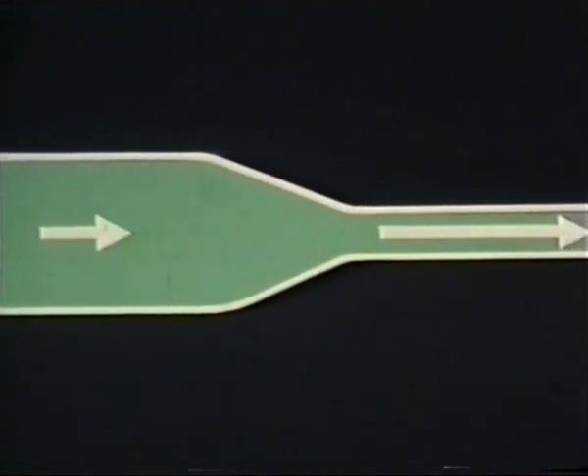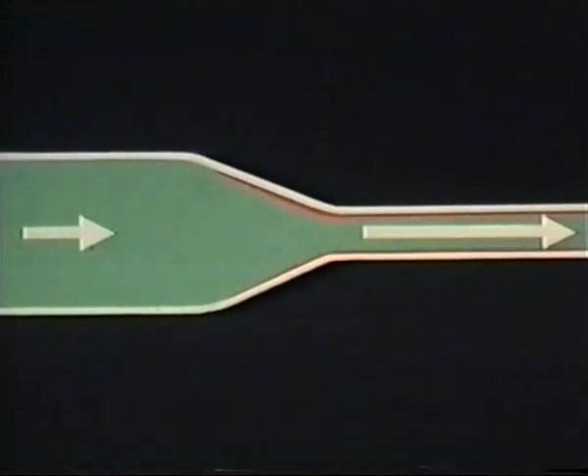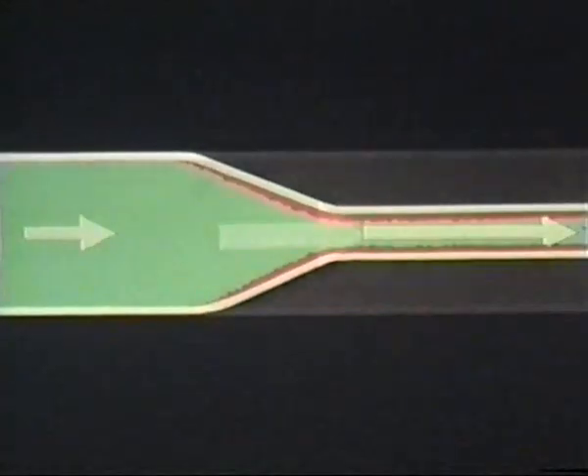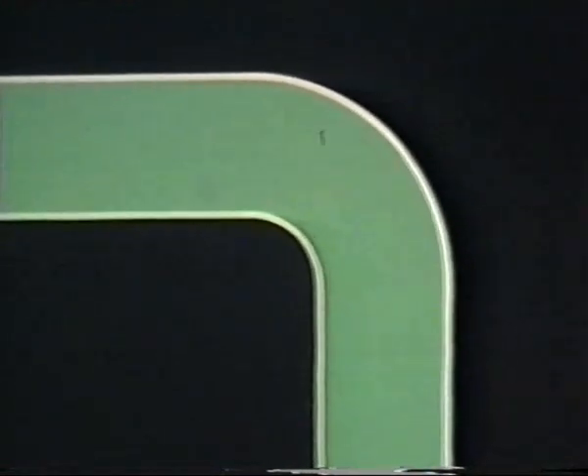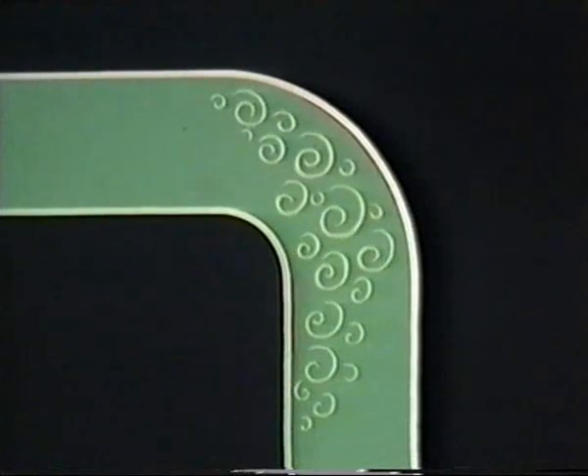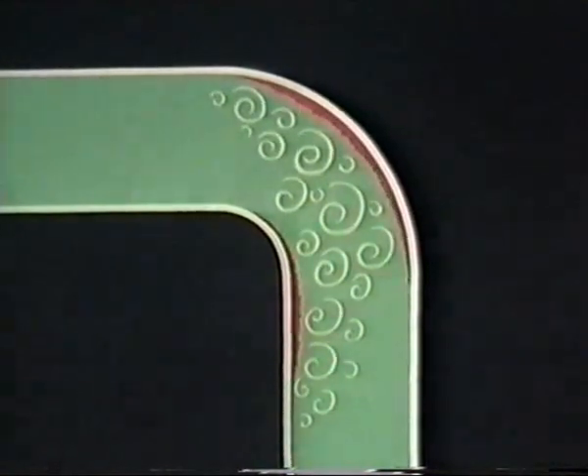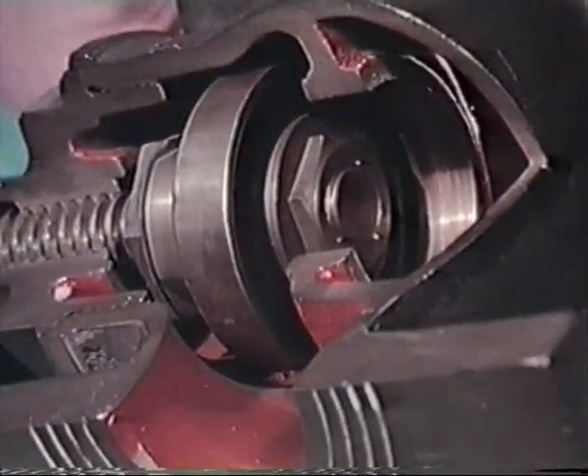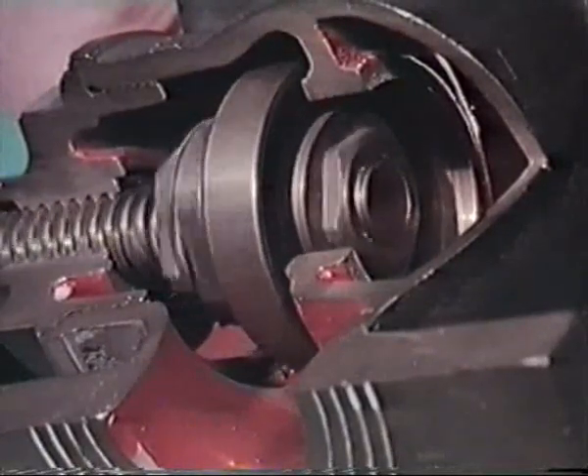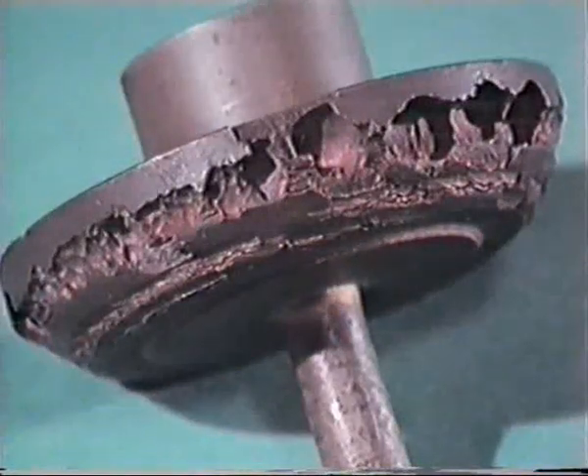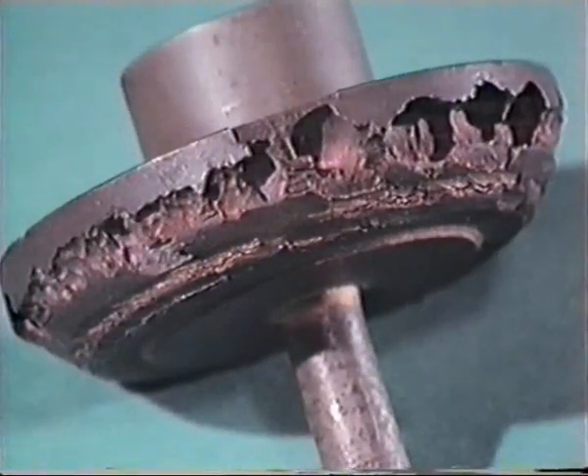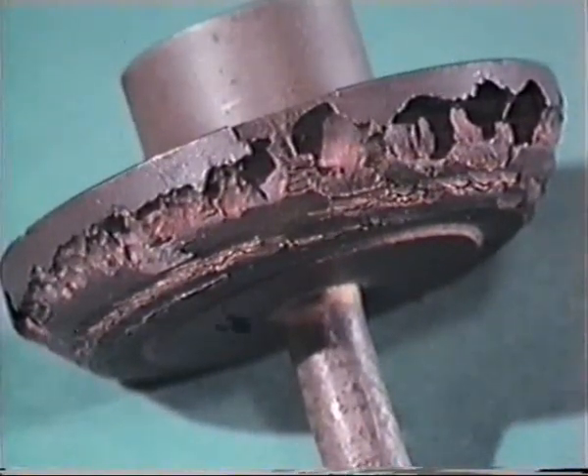Metals which corrode slowly will often be protected by the corrosion products left on their surface, so that if a liquid is moving slowly, there will be an acceptably low rate of corrosion. But rapid flow or turbulence may remove the protective layer and permit severe corrosion. This is termed erosion corrosion. It can occur in any situation which increases liquid flow sufficiently. In a seawater pipe, as a valve closed, the rush of water increased and removed the protective oxide layers. Erosion corrosion occurred. The remedy for the designer is to use either a larger valve or a more corrosion-resistant material.